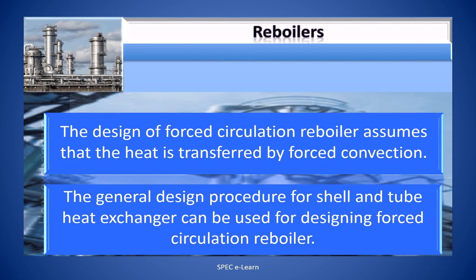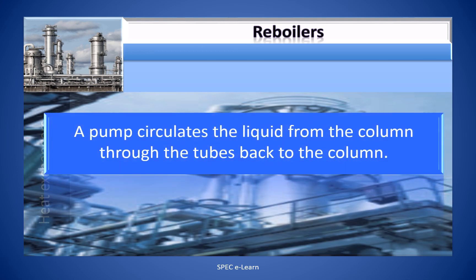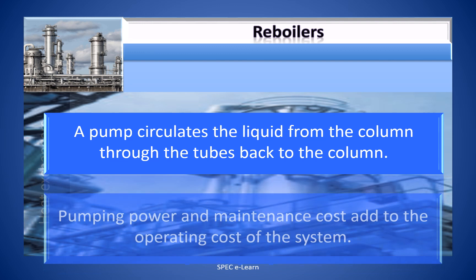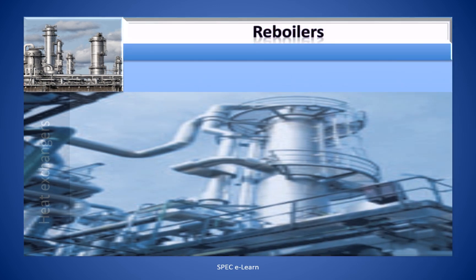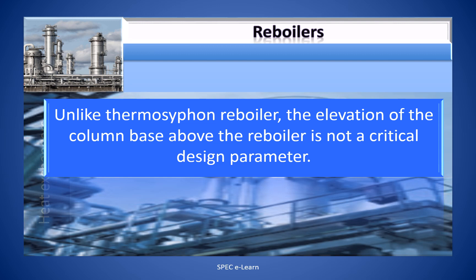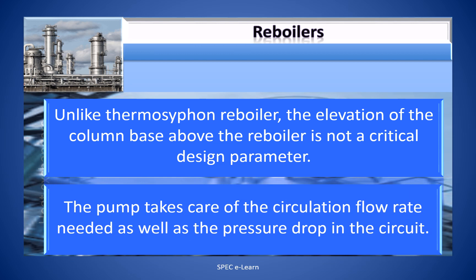The design of a forced circulation reboiler assumes that heat is transferred by forced convection. The general design procedure for shell and tube heat exchangers can be used for designing forced circulation reboilers. A pump circulates liquid from the column through the tubes and back to the column. The pumping power and maintenance costs add to the operating cost of the system. Unlike the thermosyphon reboiler, the elevation of the column base above the reboiler is not a critical design parameter, as the pump takes care of the circulation flow rate and pressure drop in the circuit.